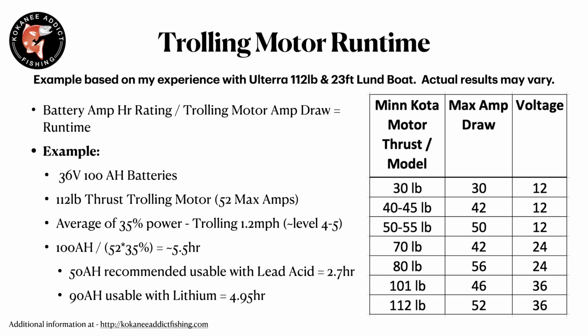So with brand new 100 amp hour batteries, when I'm draining them all the way dead, which I unfortunately have done too many times, I'm getting right around 5 to 6 hours. If I would have followed the recommendations of the manufacturers and only drained my batteries 50%, then really my usable runtime is about 2.7, about 3 hours. If I drain my batteries to that 90%, so I'm using 90 amp hours, my actual usable runtime is going to be around 5 hours out of those batteries with lithium.